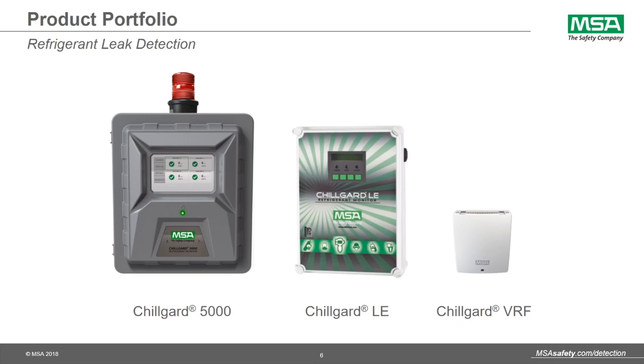MSA's refrigerant leak detector portfolio covers different applications, and I'm going to go through each of them. The Chillgard 5000 is our newest product release, with the ability to see down to 1 ppm to detect a refrigerant leak at the earliest level. The Chillgard LE is for safety compliance, and it can detect a leak at a low level of 20 ppm. And the Chillgard VRF is designed to detect a leak within occupied space.